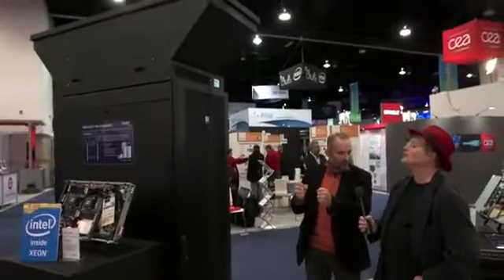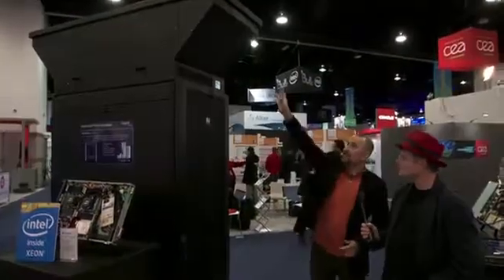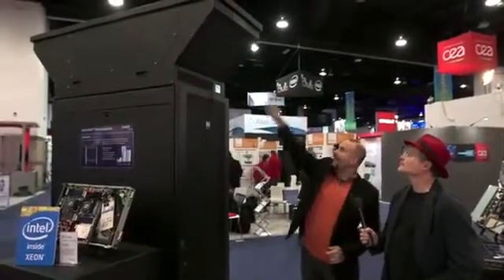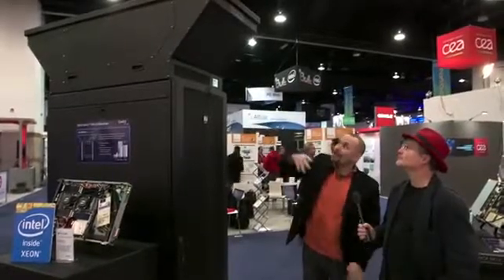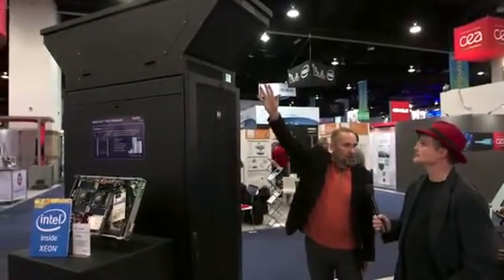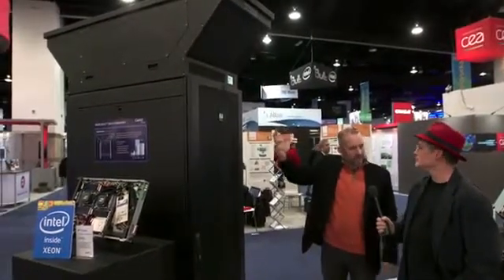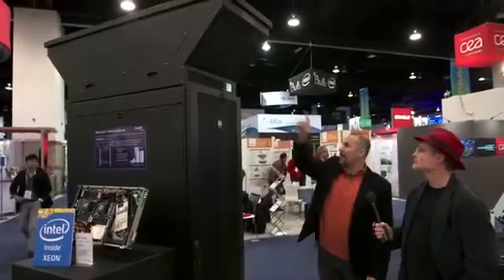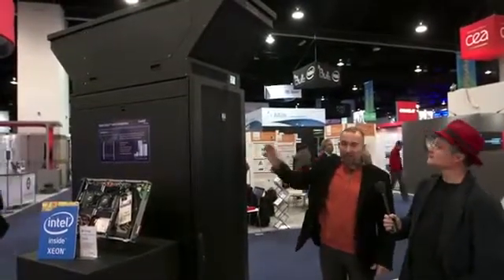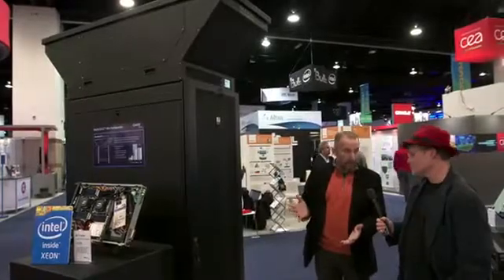This is a self-contained rack solution that allows them, at the manifold module, to plug into a liquid to air heat exchanger. This unit up on top here, the big hat that's on top of the rack, pulls air in from the cold aisle, dissipates the heat into the air from the liquid, and then exhausts it into the hot aisle.